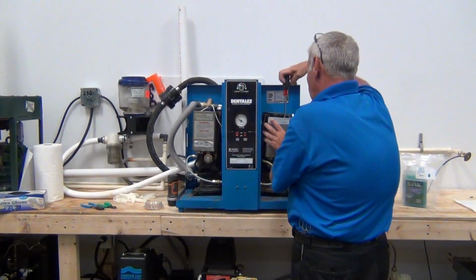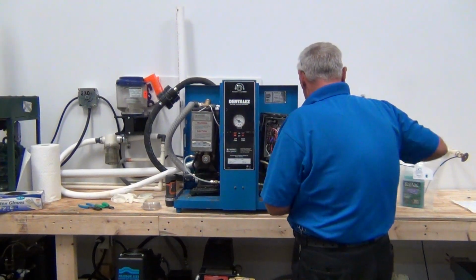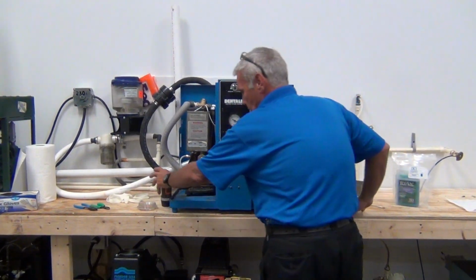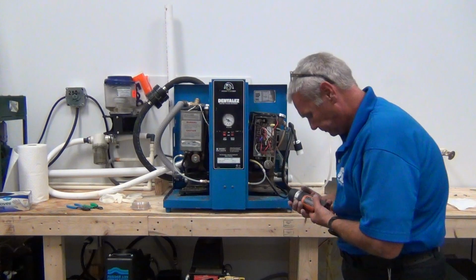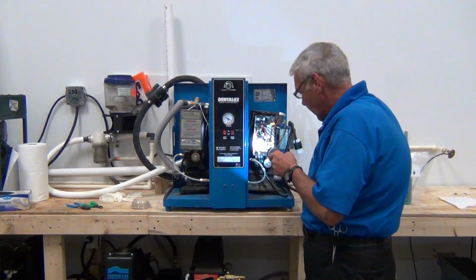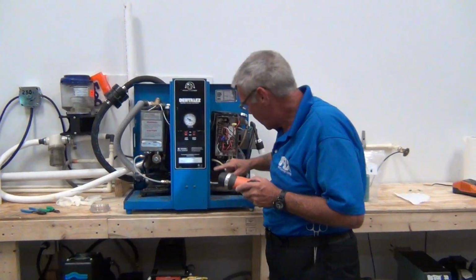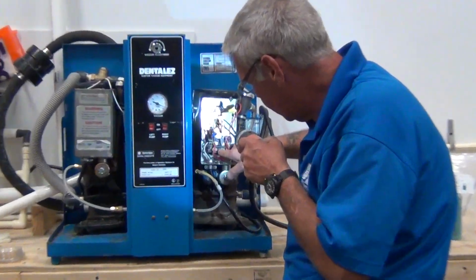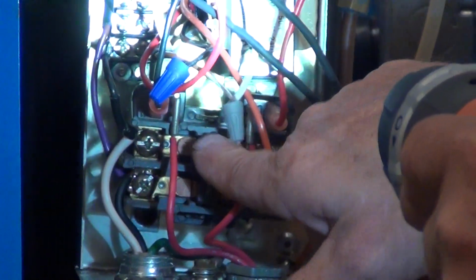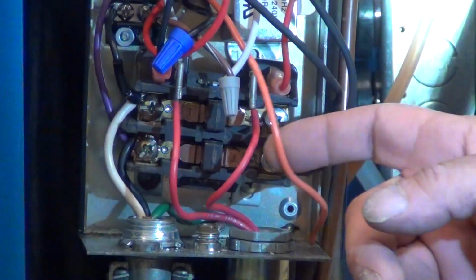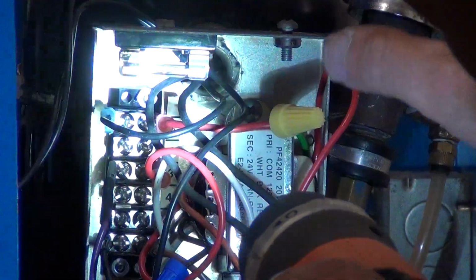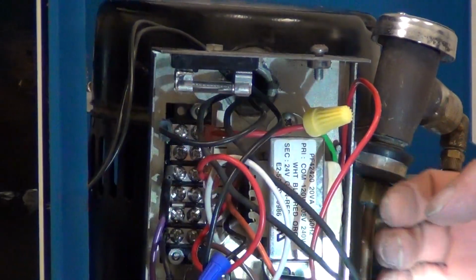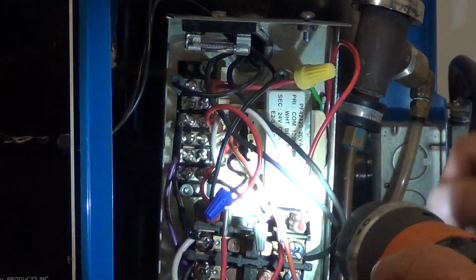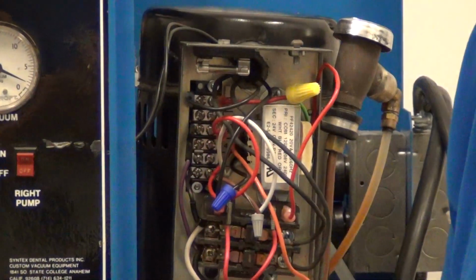We're going to remove the low voltage housing. We're going to check our wiring and our contactors. Our power's off. We're going to check our contactors for freedom of movement, sticking, carbonization, soot. Looks good. We're checking for burned wires. We'll lay our hand on the transformer and feel if it's inordinately hot. Everything looks wonderful in here.